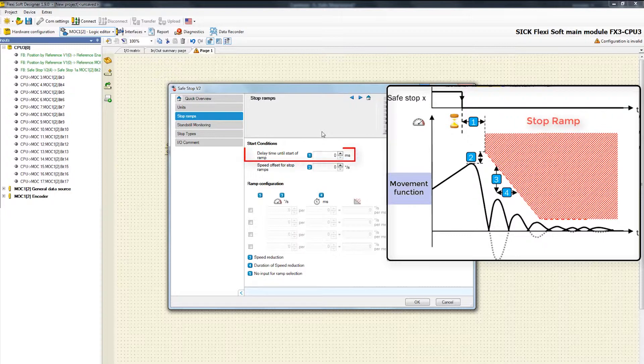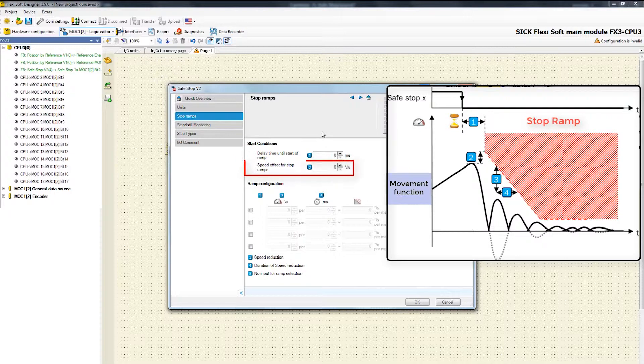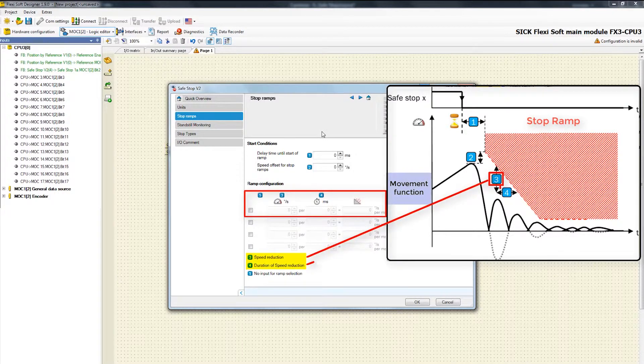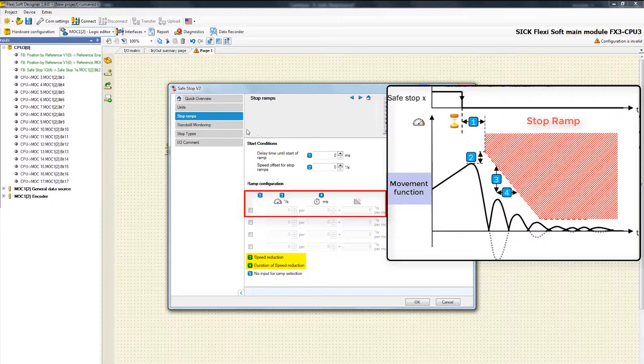First we can define a delay time until start of the stop ramp. Moreover we can set a Speed Offset — an optional addition to the start of the ramp to prevent it from being exceeded accidentally. Additionally, we can determine the slope of the stop ramps by the parameters Speed Reduction and Duration of Speed Reduction. Up to 4 ramps can be set.